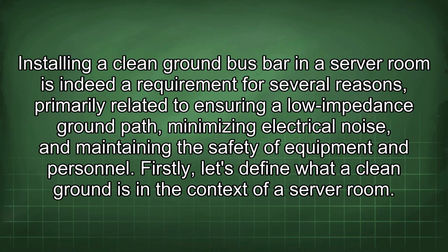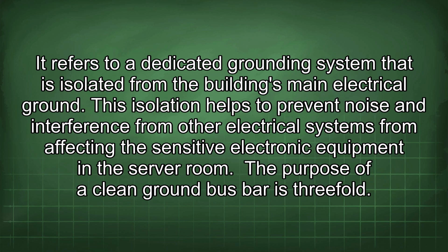Installing a clean ground bus bar in a server room is indeed a requirement for several reasons, primarily related to ensuring a low impedance ground path, minimizing electrical noise, and maintaining the safety of equipment and personnel. Firstly, let's define what a clean ground is in the context of a server room. It refers to a dedicated grounding system that is isolated from the building's main electrical ground. This isolation helps to prevent noise and interference from other electrical systems from affecting the sensitive electronic equipment in the server room. The purpose of a clean ground bus bar is threefold.